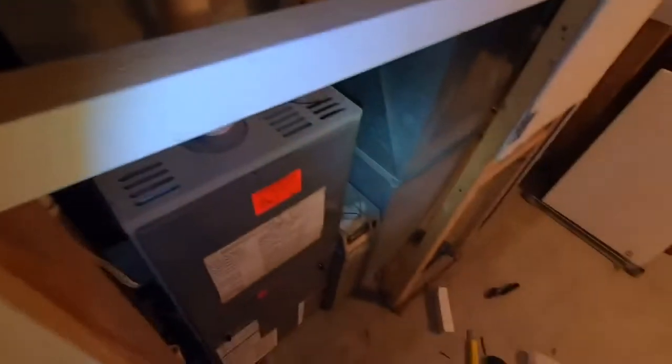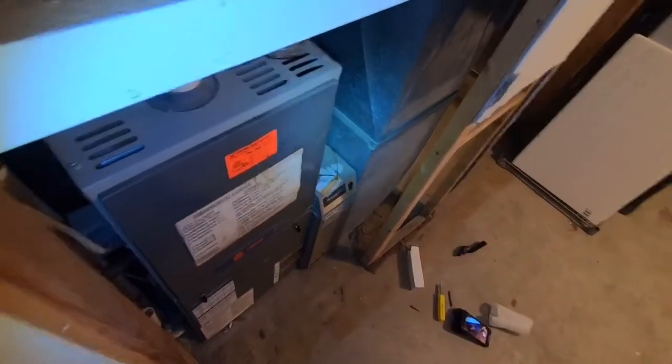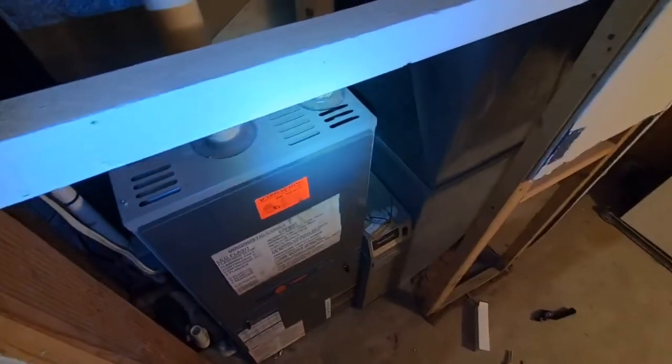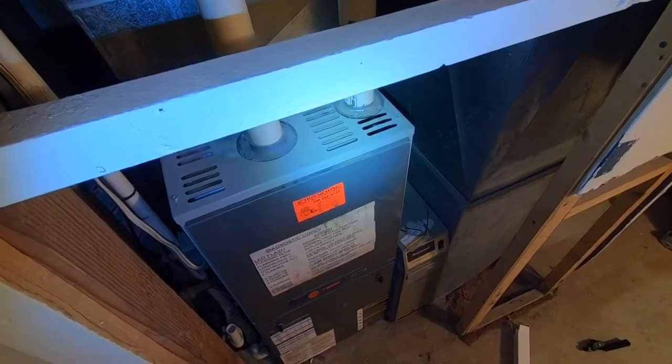And hey, Sherry, is the furnace on upstairs? It should be. Yes. Okay, I'm gonna turn it on. Now, if we look at this here, turn that light off. Okay, we've got the light blinking. That's the no call for heat.